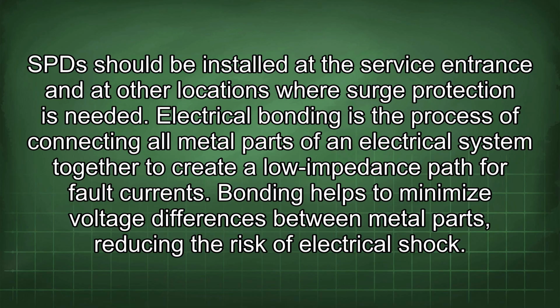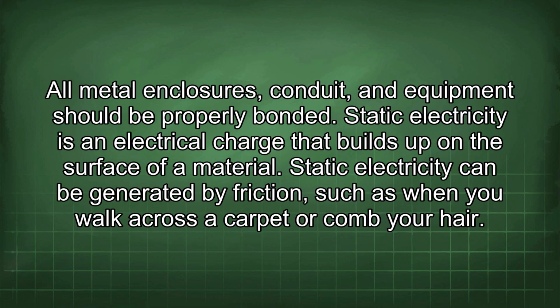Electrical bonding is the process of connecting all metal parts of an electrical system together to create a low impedance path for fault currents. Bonding helps to minimize voltage differences between metal parts, reducing the risk of electrical shock. All metal enclosures, conduit, and equipment should be properly bonded.